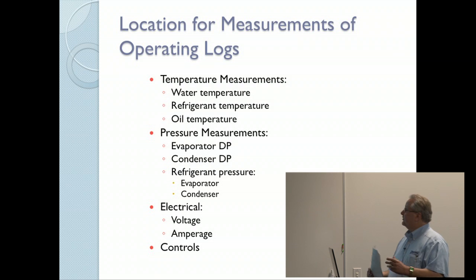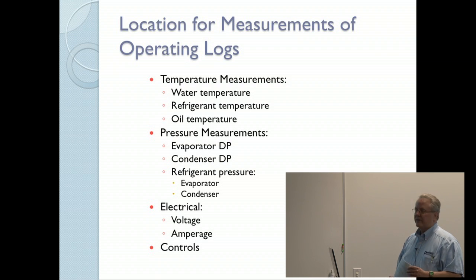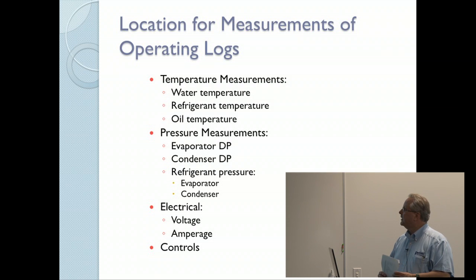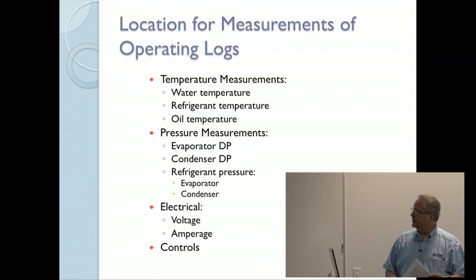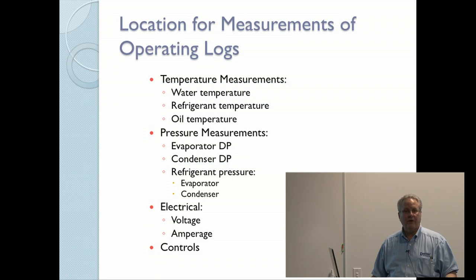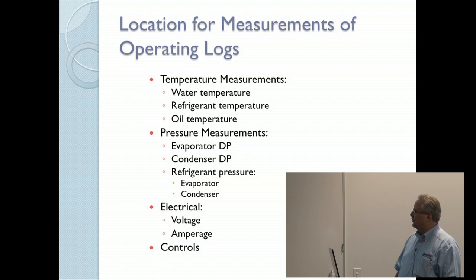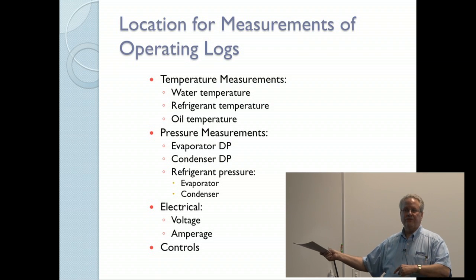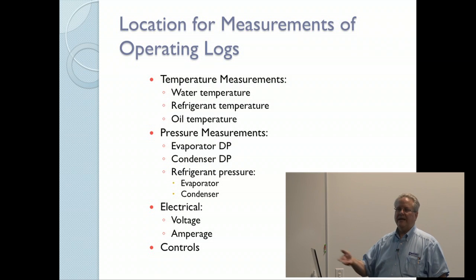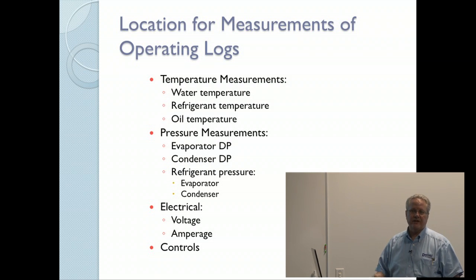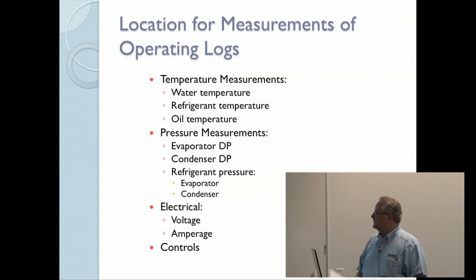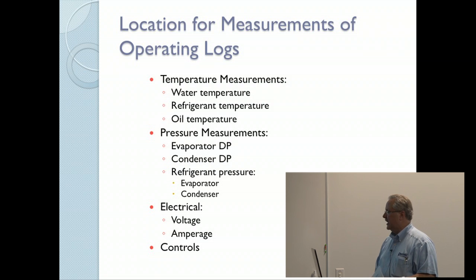Location of measurements of operating logs. Here are some of the things you're going to measure. You have temperature measurements. You want to know your water temperatures, both in and out. You want to know your refrigerant temperatures, both high side and low side. You want to know your oil temperature. You want to know your pressure measurements: the differential pressure across your evaporator on the water side, and the same for the condenser. You want to know your refrigerant pressures, evaporator and condenser. Many of the chillers today will have temperature sensors in the refrigerant circuit, and then they will extrapolate and calculate what they think the pressure is based on the saturated condition at that temperature. You want to know your electrical voltages and amperages, and you want to know your controls.